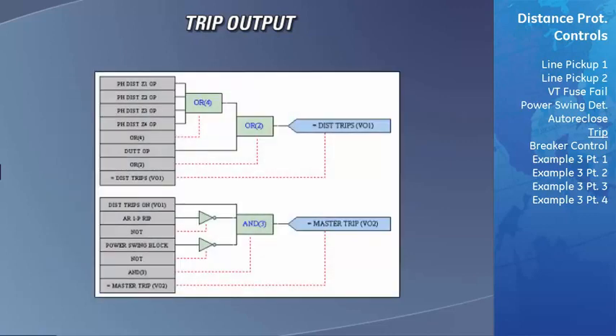All of these pilot schemes also produced output signals. The next normal process in programming a UR platform relay would be to now take all of these output operands and develop flex logic equations to customize the relay to trip when you require it to. Since there is such a large number of these operands available in the D60 and the tripping schemes can become quite complex, programming all of this logic can become daunting. This is why the developers of the D60 have produced some pre-configured logic that eliminates the need to create your own customized flex logic equations to trip and auto-reclose the breaker.